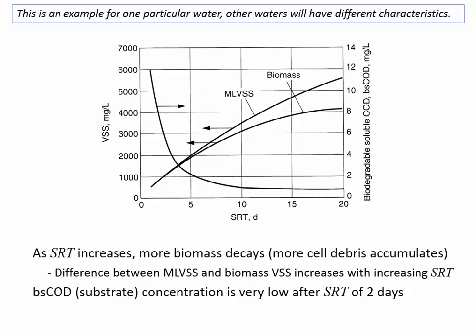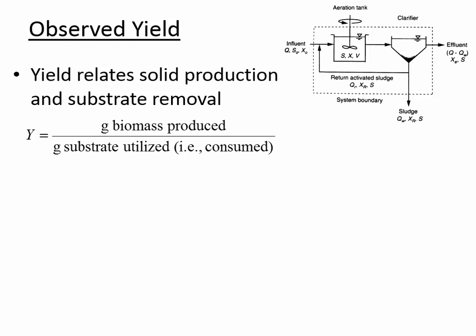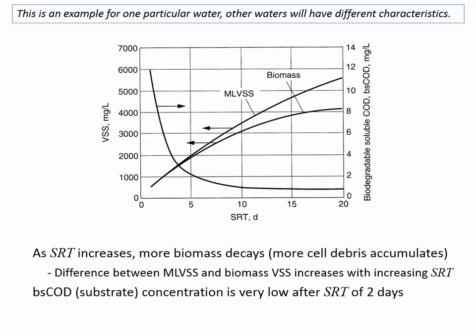So it's pretty rare for a system to have a really long extended solids retention time unless we're trying to do other things like denitrification or remove phosphorus, because there are sometimes good reasons to have a really long solids retention time if you're going for nutrient removal. We get into that in chapter 8. Any questions about this figure before we move on? No. All right, we'll take a break in about 5 minutes.